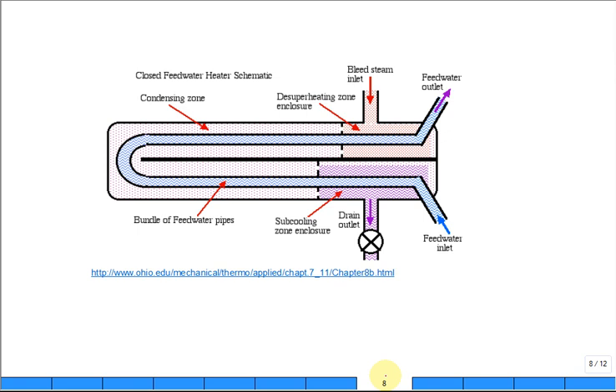This is another illustration out of his online textbook. As the feedwater comes up, there's a plate right here that prevents it from going up, but it forces it to go into tubes. There could be a lot of these tubes. The tubes go down, they turn around, and they come back, and then they go into another plate. This is like a manifold and a manifold. But when the tubes come down, the flow is really cold. So it's the best place to take the liquid condensate out. When the feedwater is coming out, it's the warmest it's going to be. And that's probably a good place to have the hot steam bleed in, bled off from some place like between two turbine stages.